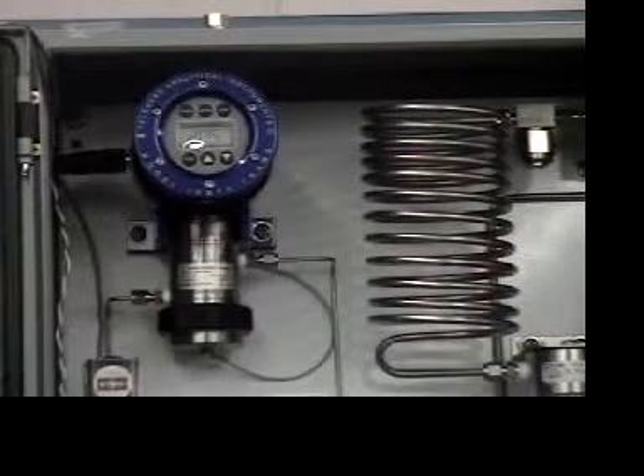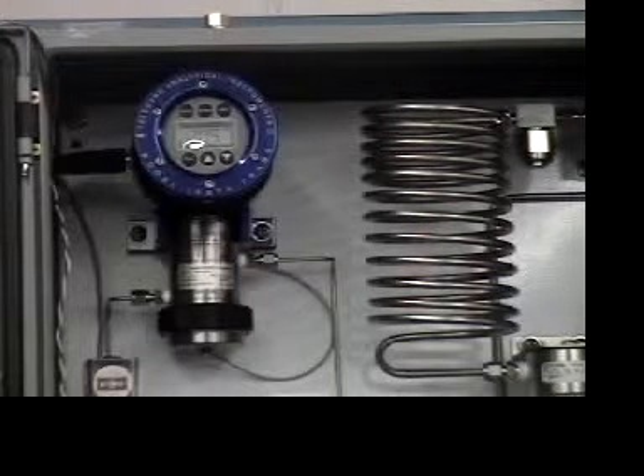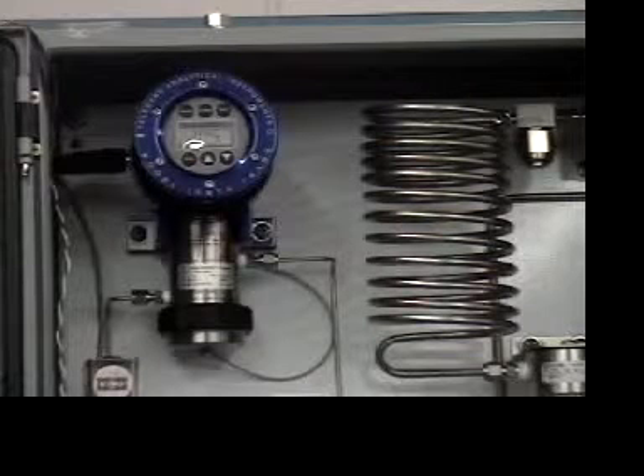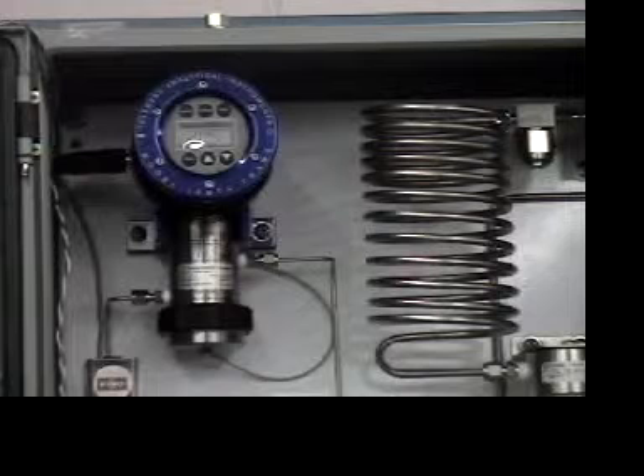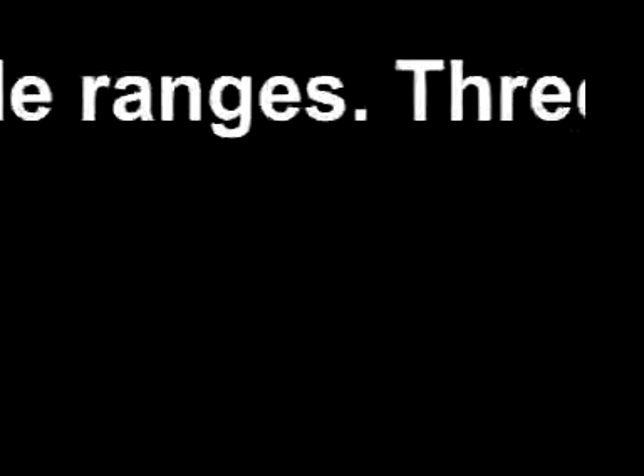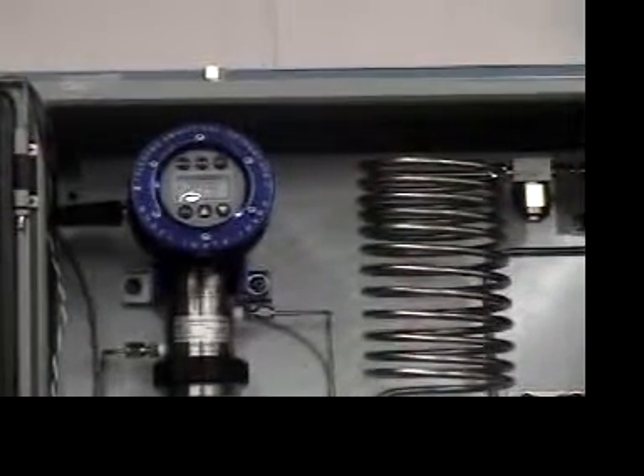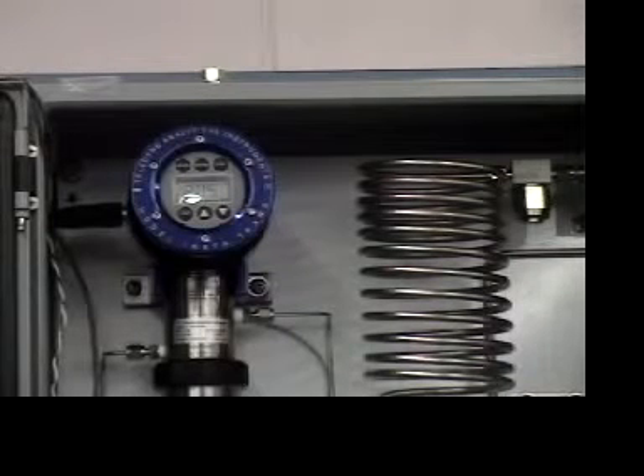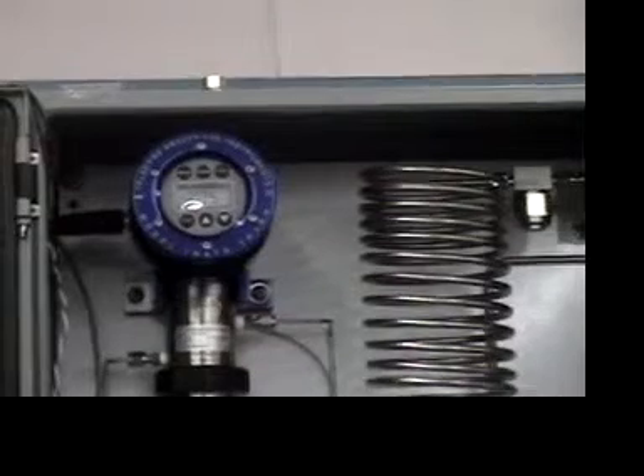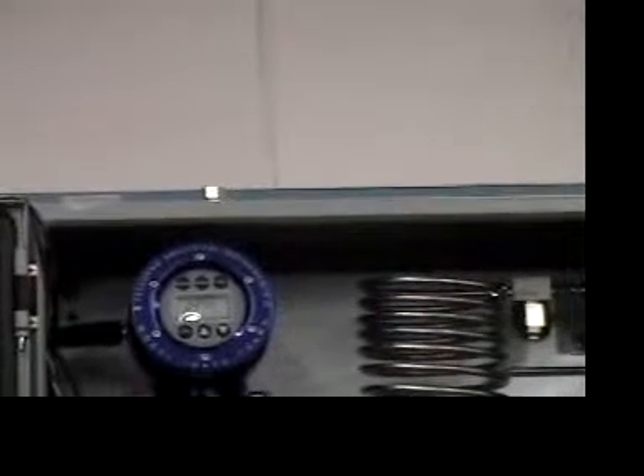The InstaTrans transmitter is a loop-powered device which provides a 4 to 20 milliamp DC signal. This 4 to 20 milliamp DC signal is proportional to the amount of oxygen that is at the sensor at any given time. If there is no oxygen at the sensor, your analyzer will be reading 0 and your output will be 4 milliamp DC. If you're reading 25% oxygen, that would be the full scale range, and that would be 20 milliamps. If you're at mid-scale, you can expect to see 12 milliamp DC output.